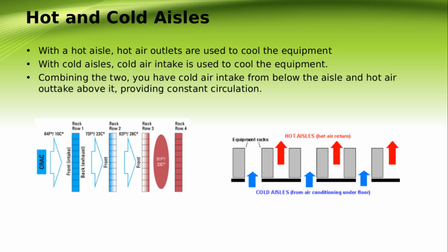So the hot and cold aisles. Data centers and server farms can make use of an alternating arrangement of server racks, with alternating rows facing opposing directions. Fan intakes draw in cool air vented to the racks facing the cold aisles, and then fan output of hot air is vented to the alternating hot aisles for removal from the data center.